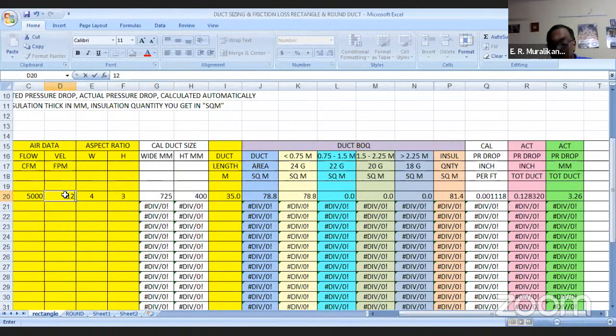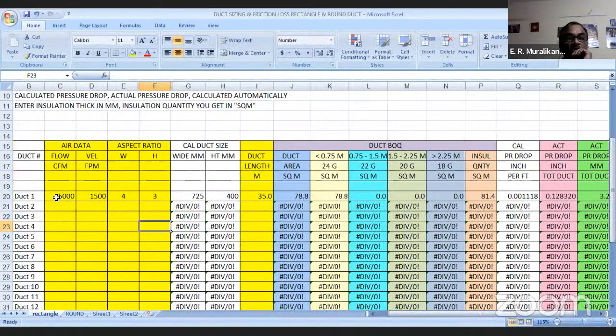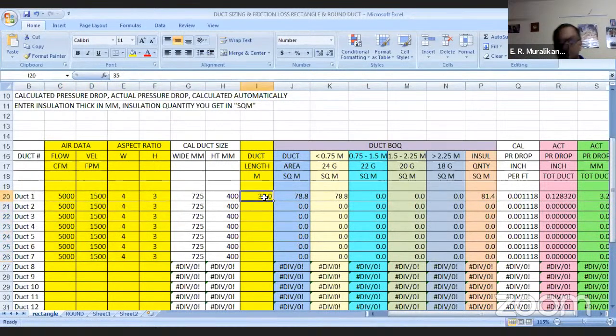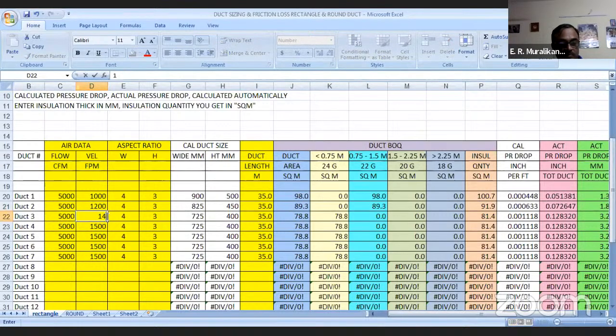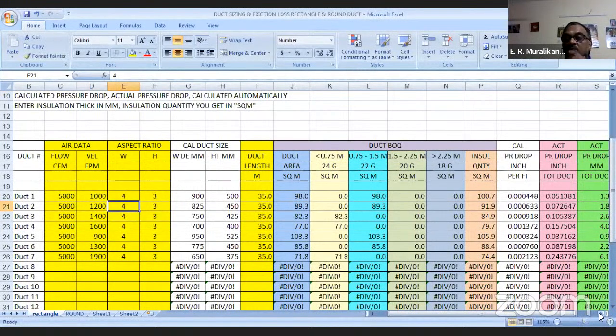Correct? See, 1200 FPM, CFM is the same, duct length is the same, 35 meters, and actual pressure drop is 1.85 mm. Now if you put 1500, it's coming to 3.26 mm. If you're not able to understand, I will copy this further down the line and put different velocities and show you. This 35 meters I'll keep the same. CFM is the same. I put here say 1000, then 1200, then 1400, now 1600, now 900, then 1300, 1900. See how the pressure drop is changing.